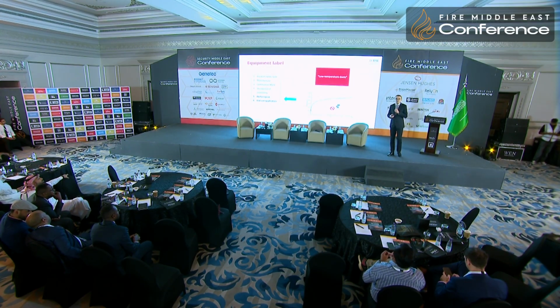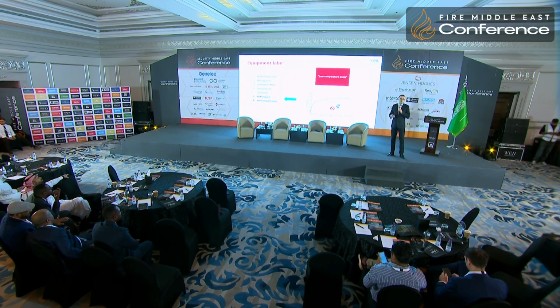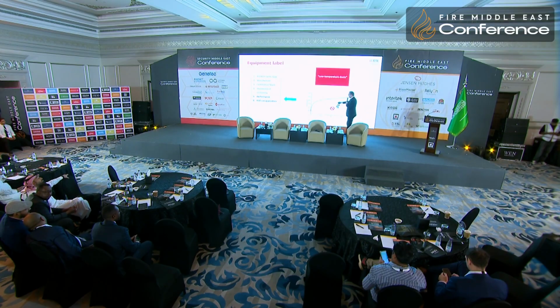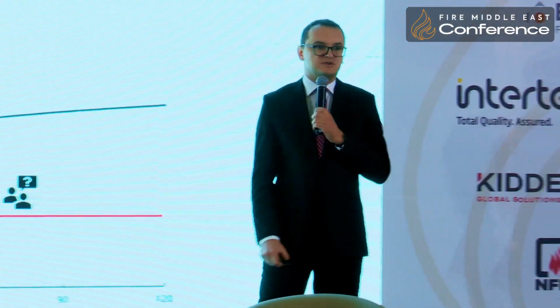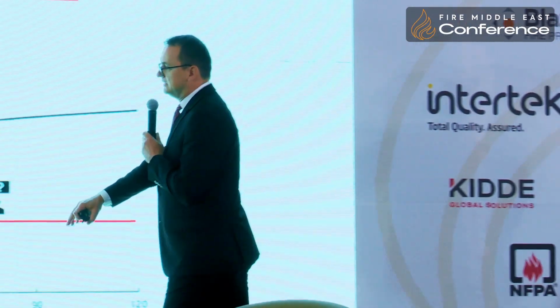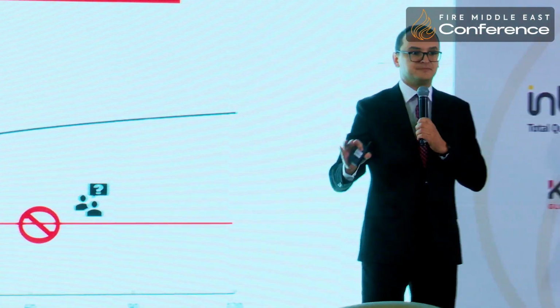You might have come across a situation when the market was offered so-called low temperature ducts, which were tested to a lower temperature value. Explaining it practically, when we see a fire-rated duct, we expect that at the 30th minute it was already subjected to a temperature of 800 degrees, and at the 90th minute it will be more than 1000. But in the case of low temperature ducts, the temperature increased during the test, stopped at 400 and just remained there, and the duct was proved to meet that requirement. Maybe it can be used for some design, if there is such an objective for the ventilation construction, but definitely not for naming or claiming that such construction is fire rated.